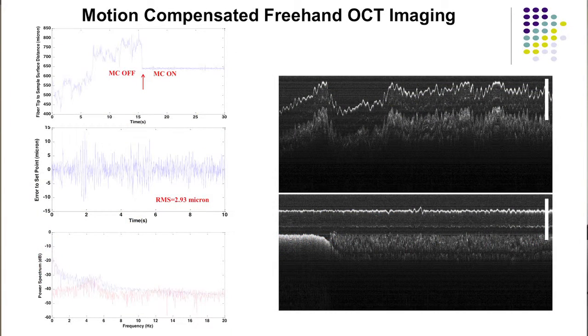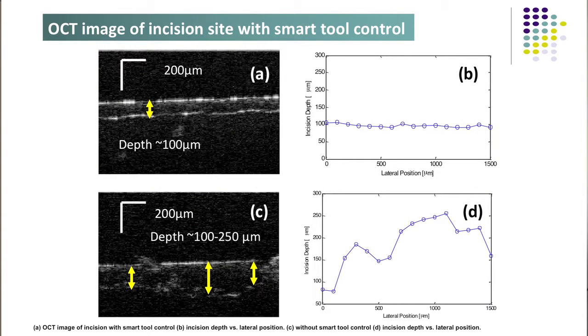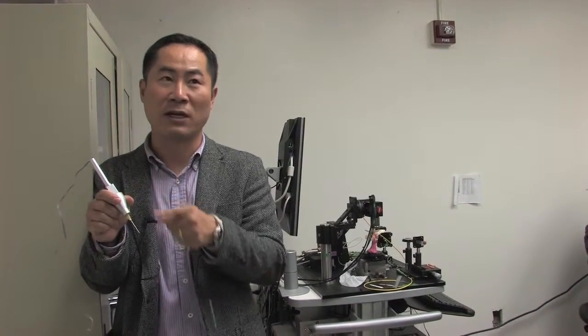What this tool would do is the surgeon will use it like a normal surgical pick, but without them really getting involved with it, it knows exactly how far you are from the retinal surface. You can sense the movement of the hand, because when it moves, the distance between the tool tip and the retinal surface changes. Using OCT, we can actually see how much it moves, and using the motor, we can compensate for those movements.